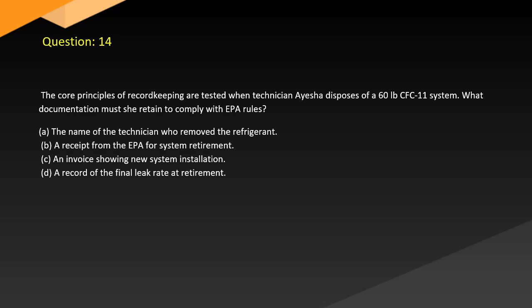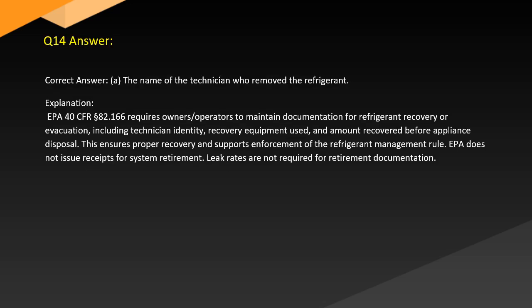Answer. Correct answer. A. The name of the technician who removed the refrigerant. Explanation. EPA 40 CFR 82.166 requires owner-operators to maintain documentation for refrigerant recovery or evacuation, including technician identity, recovery equipment used, and amount recovered before appliance disposal. This ensures proper recovery and supports enforcement of the refrigerant management rule. EPA does not issue receipts for system retirement. Leak rates are not required for retirement documentation.